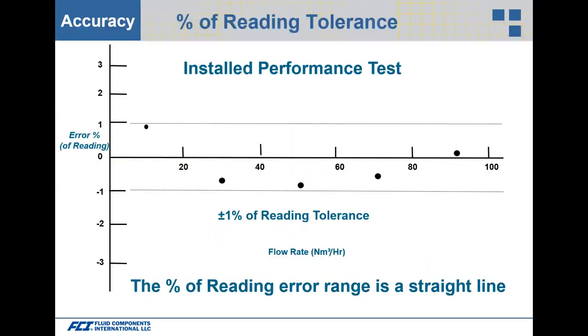On the chart, the left-hand side shows percent error based on reading — ±1% of reading across the flow range from 20 up to 100 normal cubic meters per hour. The repeatability is just one percent, and all the dots line up within that one percent band.